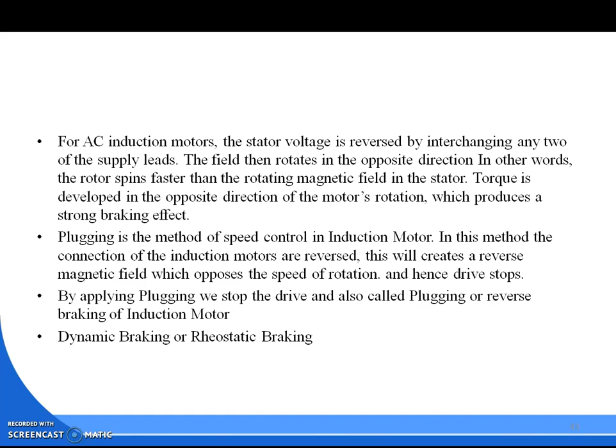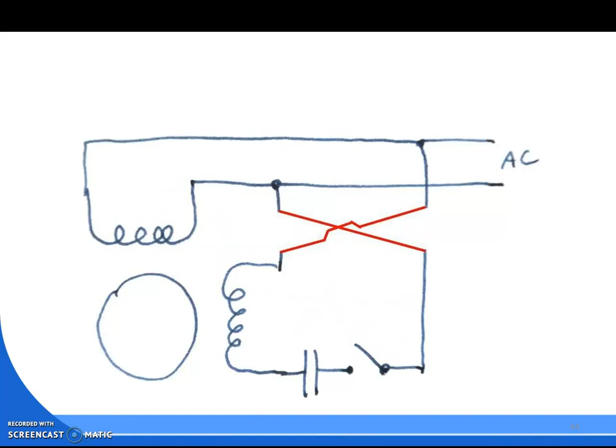By applying plugging, we stop the drive. This is also called plugging or reverse braking of an induction motor, as opposed to dynamic braking or rheostatic braking. Here in the AC induction motor case, this is connected here, and this is connected here, so that means it is in reverse. This is connected to the first line and this is connected to the second, so the supply voltage here is reversed. This is called AC plugging, the plugging mechanism in case of AC.